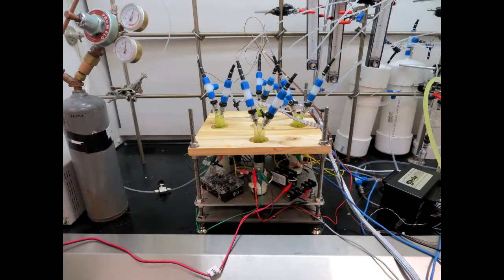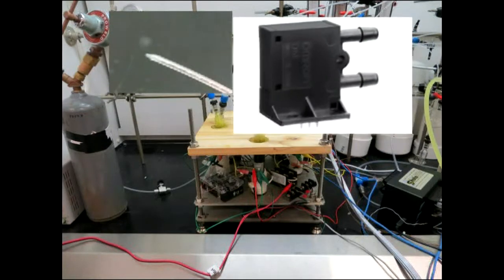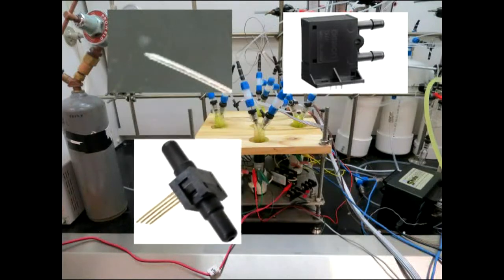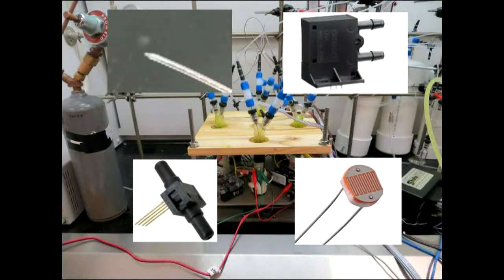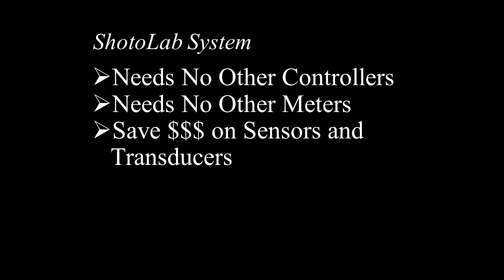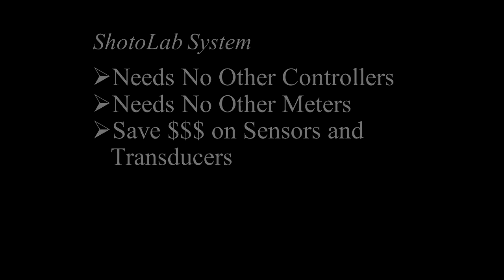Each of the reactors has a thermocouple made with thermocouple wire, a flow meter, pressure transducer, and a light sensor to monitor the reaction progress. You can watch our individual video showing how each of these components was connected and configured to the Shoto Lab system. The greatest benefit of the Shoto Lab system is it allows you to use these sensors without the need for any other controllers or meters. It allows the use of sensors at about 1/10 the cost of your traditional lab sensors.